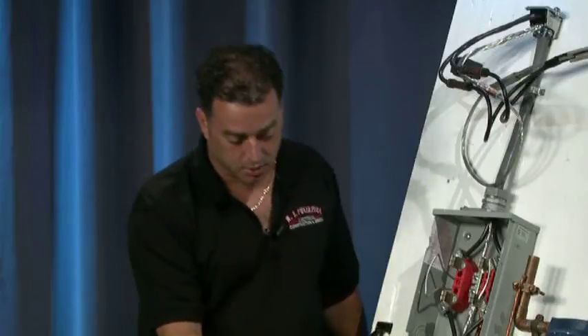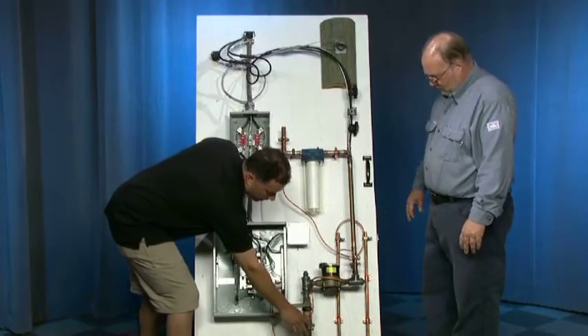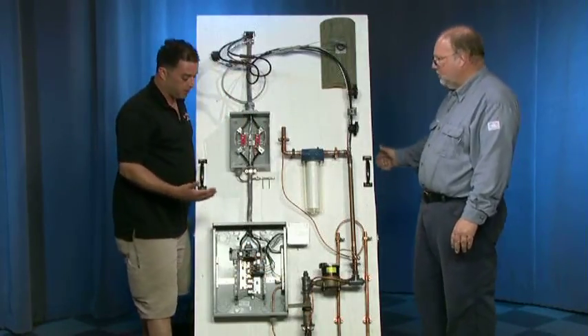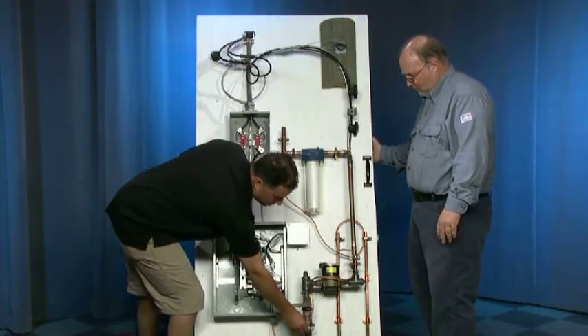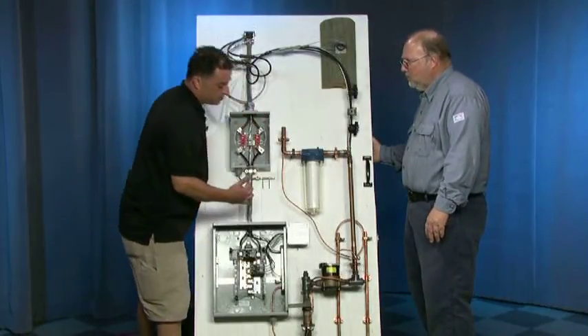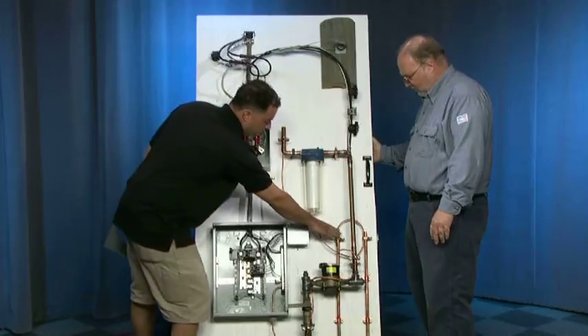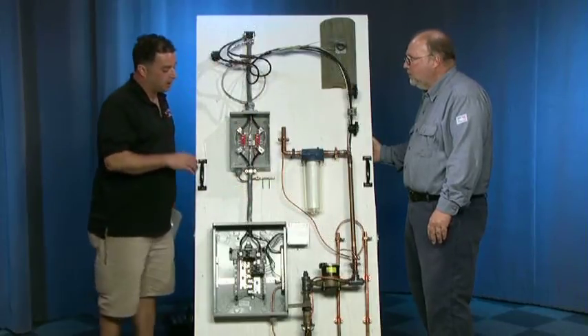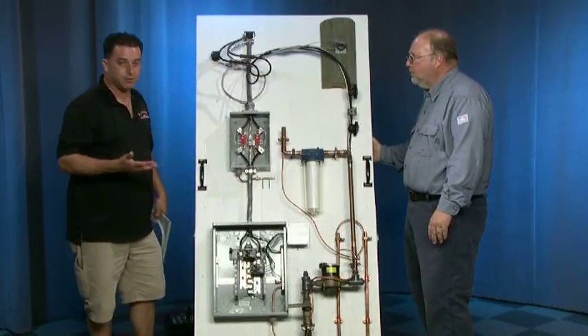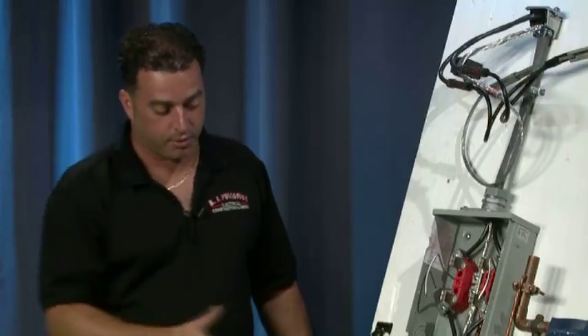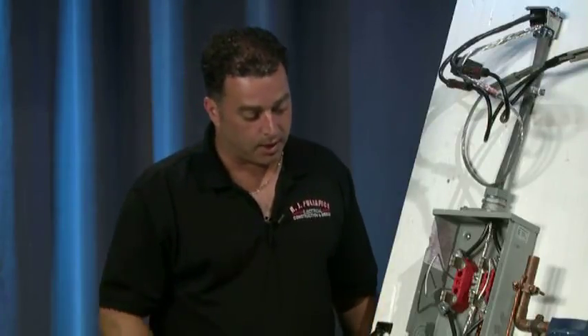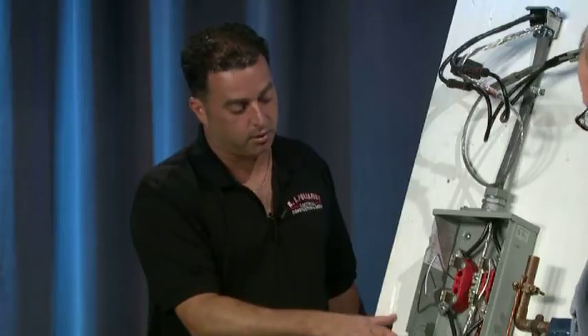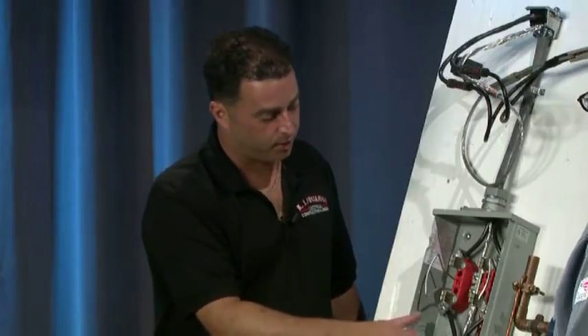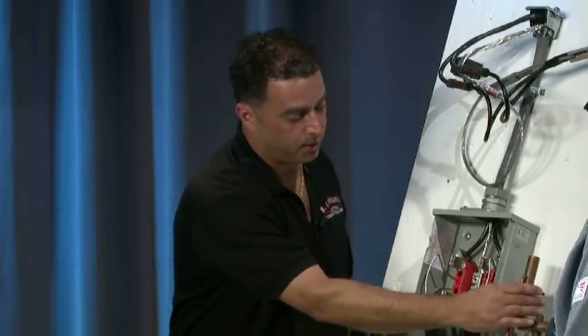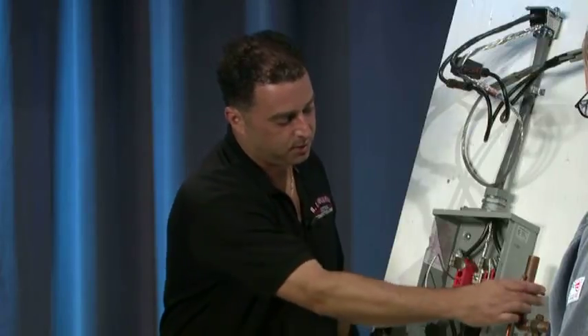Check your grounds, most importantly your water ground. In some towns the water is very hard and these clamps will actually rot off, leaving you with no connection. Older homes probably don't have ground rods, so that can be added as a backup to your water ground. If they're present, we check that they're connected properly, just like jumping out your water meter. All these connections need to be clean and tight.